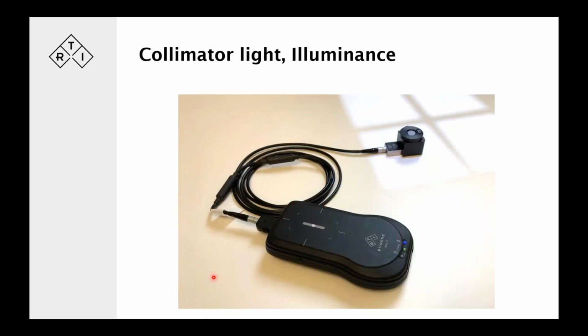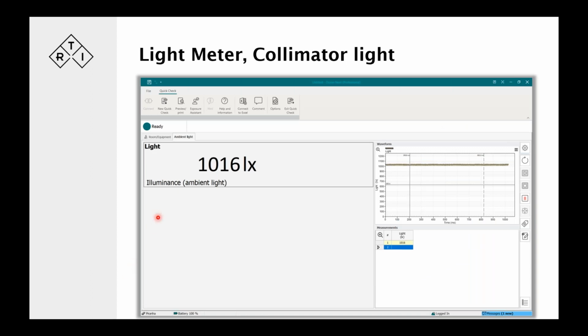For the collimator light, we use the diffuser, of course, and place the probe in each of the 4 quadrants, and also in the ambient, with and without the ambient light, the collimator light switched on, to get the difference in between, and you go. And this is then the reading of the ambient light. You get it in lux. You can see that it actually does stabilize and then terminate the measurement, and so you have a stable reading for that value.